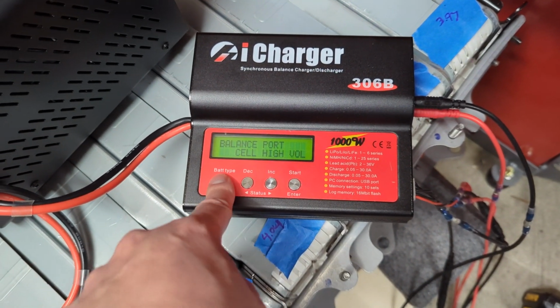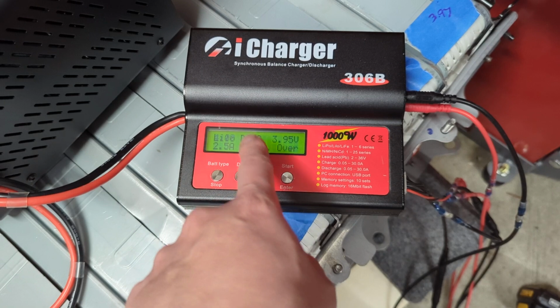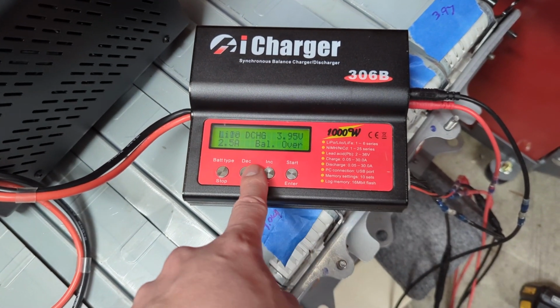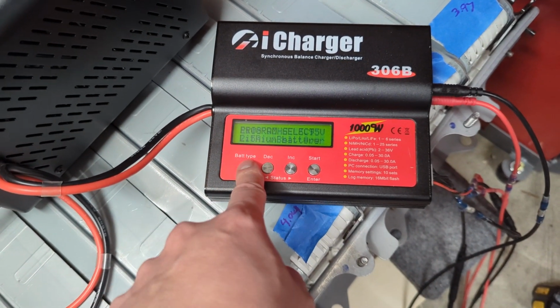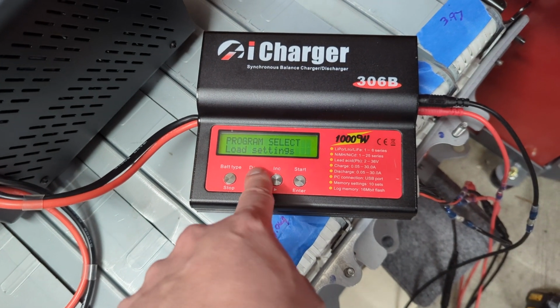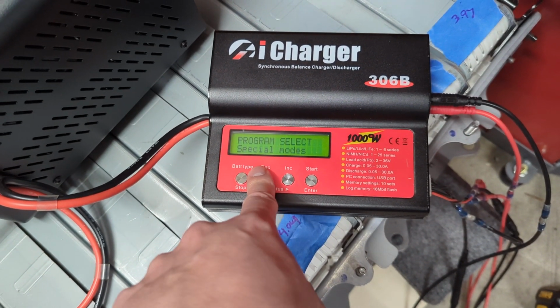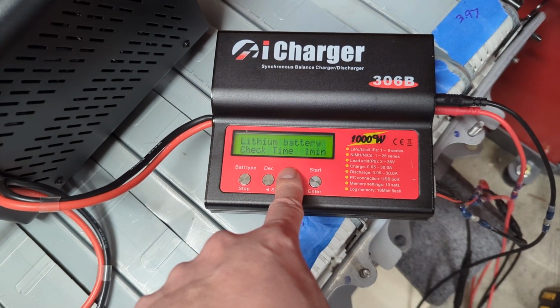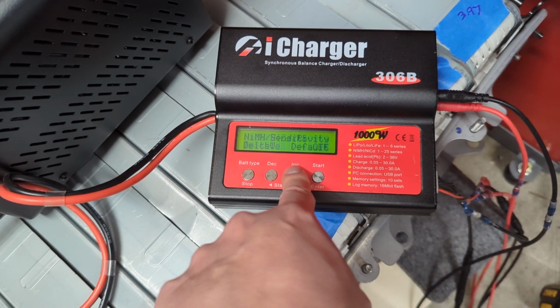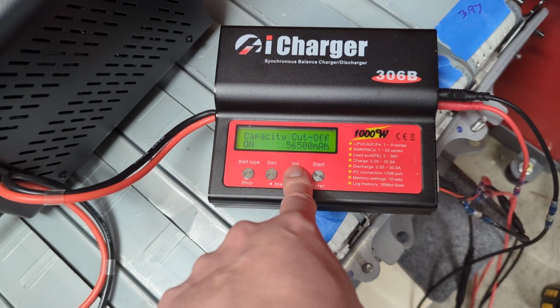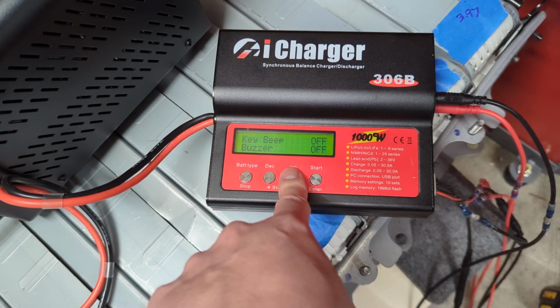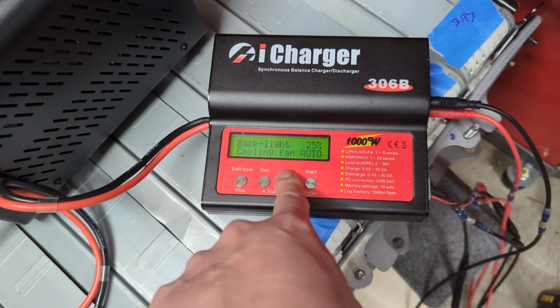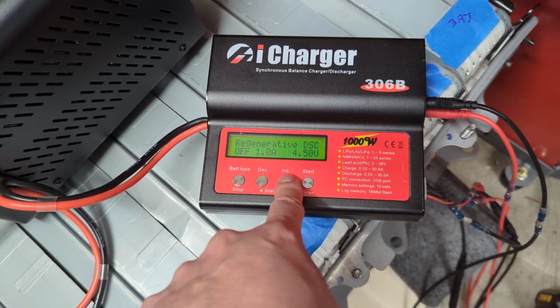So it took me a while to figure out that if you're getting balance over error messages, it's because your limit here is set too low, because it's a safety cutoff - it goes into the safety cutoff to determine that it's fully charged.